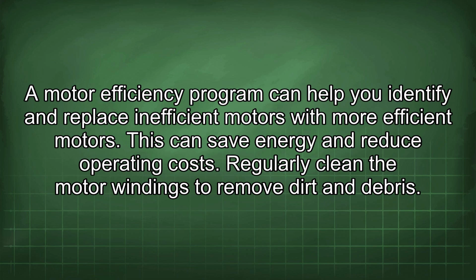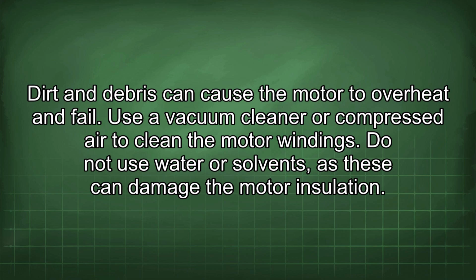Regularly clean the motor windings to remove dirt and debris. Dirt and debris can cause the motor to overheat and fail. Use a vacuum cleaner or compressed air to clean the motor windings. Do not use water or solvents, as these can damage the motor insulation.